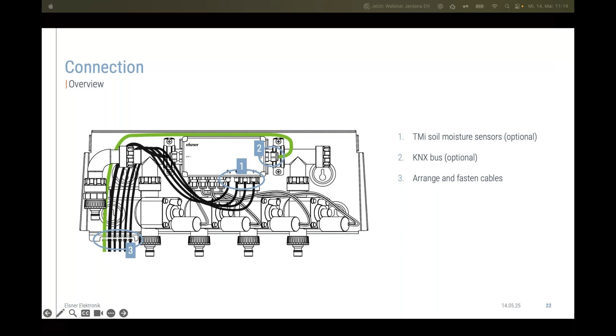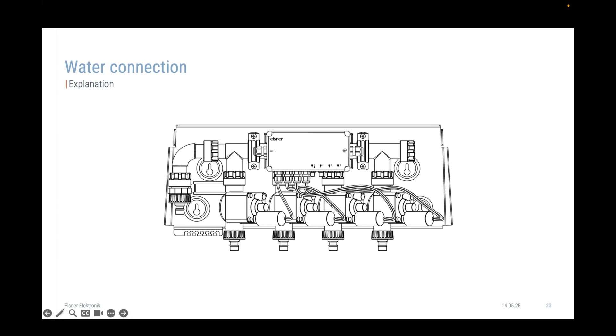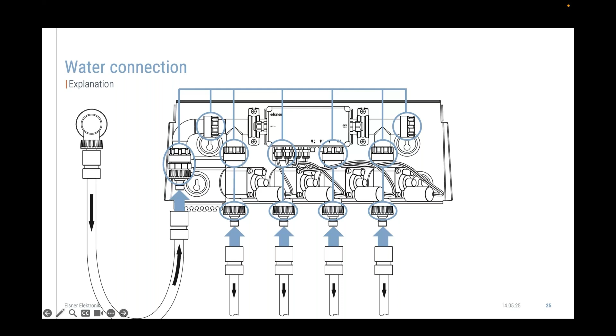In the last portion of the presentation, we had a look at the cable management for the KNX wires, for the sensors, and now we're going to have a look at how the water piping is working. So it's very important that all the screw connections of the water supply are checked and that they are hand tight. It's really, really important that you check them afterwards. Due to transportation, due to some vibrations whatsoever, they can loosen up, and it's of utmost importance that you check those once you have the system installed. So you can connect the different hoses to the different connectors that we're supplying with the Gardena itself. So really, plug and play is taking on a new meaning here. All the standard water plugs will work with our system.